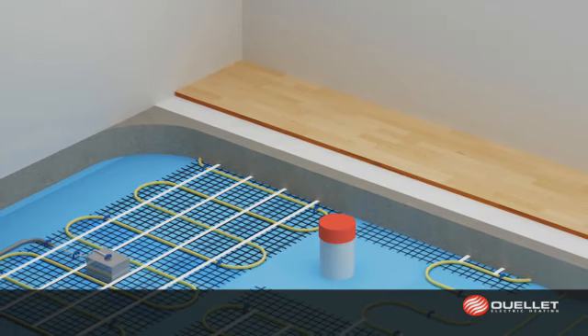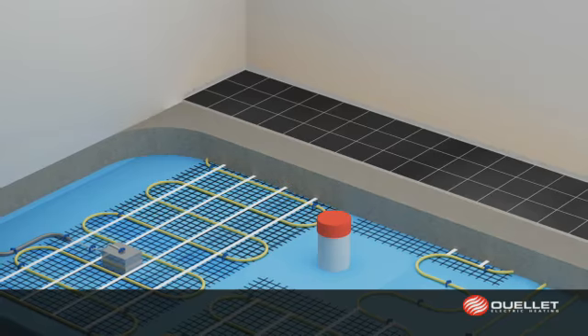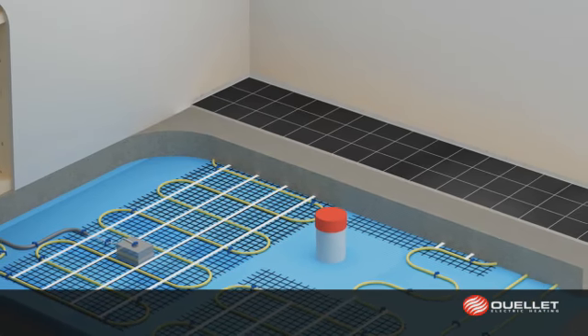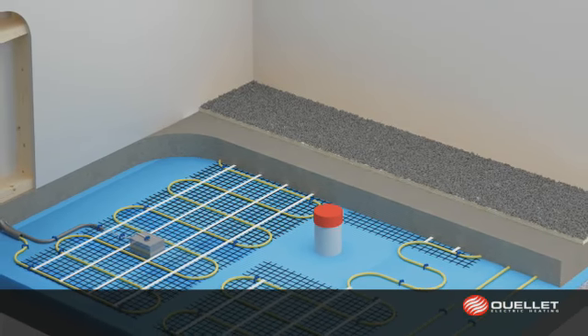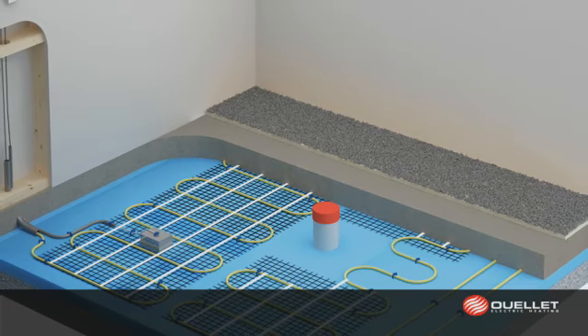It's possible to install many types of floor covering directly over the heated concrete slab. Verify the product's compatibility with the manufacturer. We're now finished installing the heating cable for concrete, and it's now time to connect the system to the thermostat. Ouellet offers programmable and non-programmable thermostats to control your heated floor.